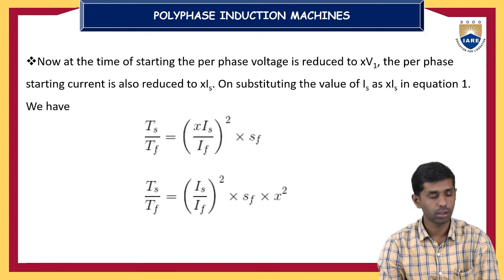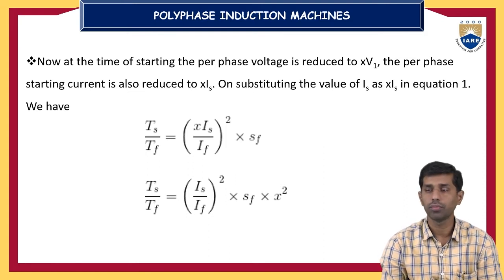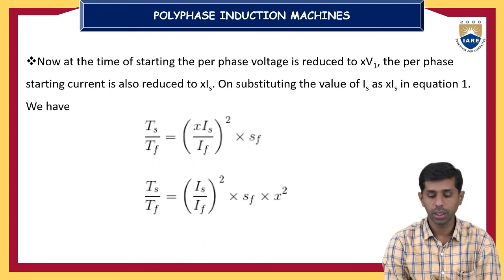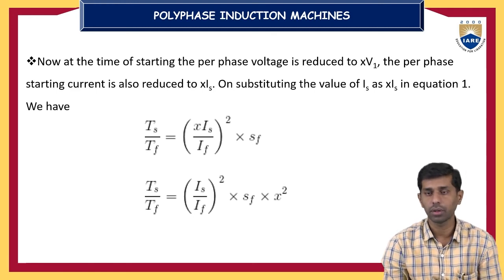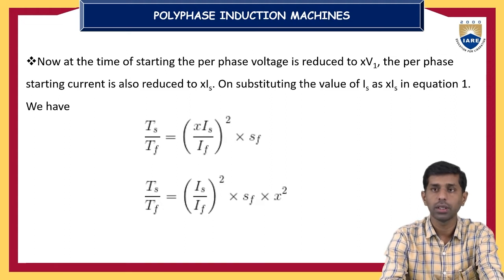So resistors are connected in series with each of the phases. Obviously there will be a voltage drop across the resistors. I am considering here x times V1 as the voltage drop in each phase at the time of starting. Similarly, the current is also reduced to x times the starting current.